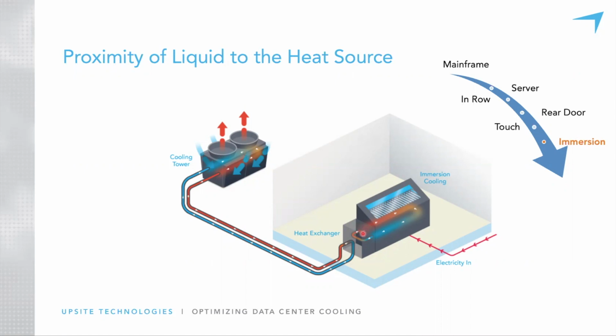But these liquids pick up the heat from all the components that are in that tank, and then with another heat exchanger, pass that heat to another liquid that is taking it out of the building. There might be a chiller involved. In most cases, there isn't. Depends on how the system is set up, but heat leaves the room through liquid and is then ultimately rejected to the atmosphere as before.